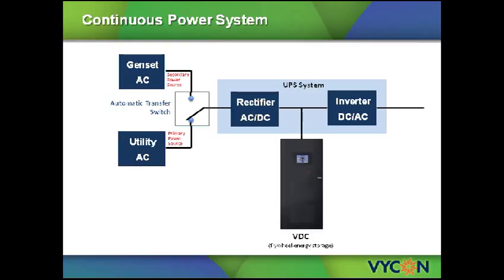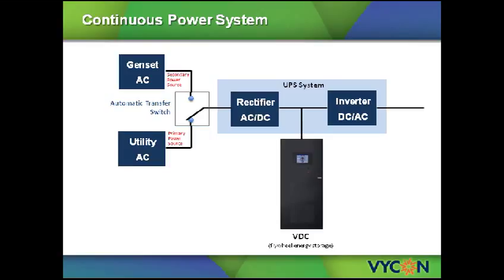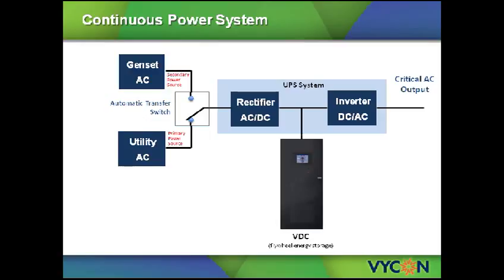Components of a continuous power system include an uninterruptible power system, often referred to as a UPS, which provides conditioned power to the critical load; the utility supply, which is the primary power source; a standby generator that provides long-term backup power during a utility outage and is considered the secondary power source; an automatic transfer switch, referred to as the ATS, that switches the power source to the UPS from the primary source to the secondary source and back; and the flywheel energy storage system that provides the short-term backup power during the time that the primary source is lost until the secondary source is available.